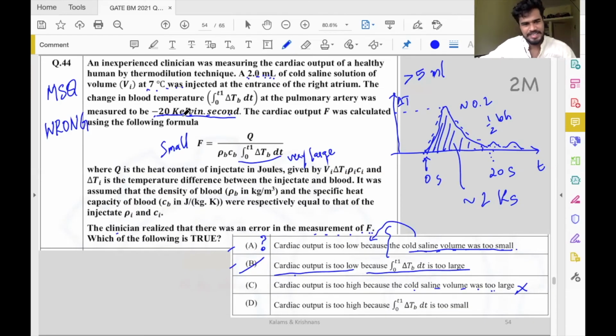First thing. Second thing, see, this minus 20 Kelvin per second is an intermediate variable. Usually one is not concerned about this value at all. One is concerned about this value, measured F. What is likely going on here is that you are supposed to use a saline solution at 0 degrees. But I think due to the temperature of the room as well as improper handling by the clinician, that 0 degrees became 7 degrees Celsius before injection. Now the question is, if the clinician knows that the injected saline is at 7 degrees Celsius, the clinician should be able to correct for it. So this is written as 7 degrees Celsius, but whether that is known to the clinician, and whether the clinician accounted for the term here in this temperature measurement, is not clearly stated.